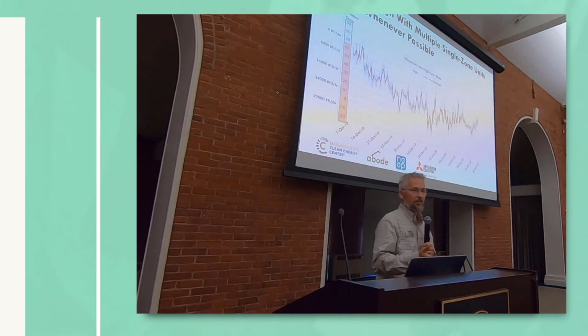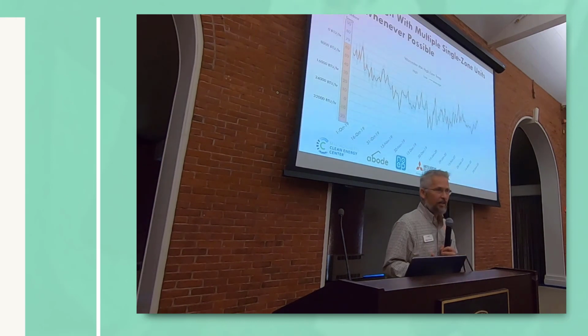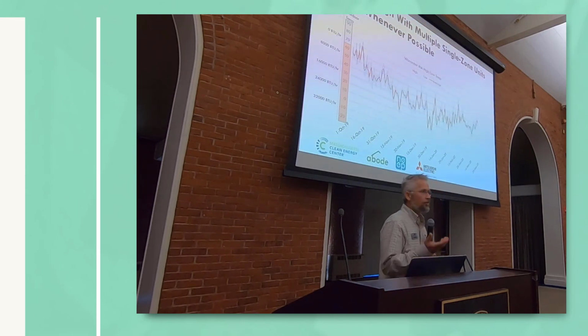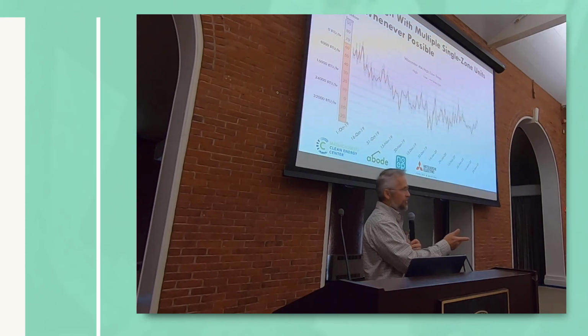And so all the different heating systems that get tested against that, you can look at their efficiencies and gauge them. If you look at single zone systems, it's very easy to find, and in fact the standard in Maine is to have HSPF 12 as a minimum to receive a rebate. There are many heat pumps that hit HSPF 12 as singles, but multi-zones, only the highest performing ones are above 10. There are some multi-zone circumstances where you can get to 11, and I've got 2 minutes, but you can see that comparison. Part of it has to do with the way that they're tested in terms of their efficiency, because they require that one of the indoor heads is shut off during the course of that test.